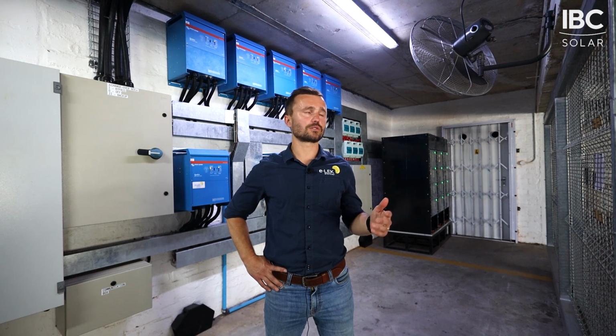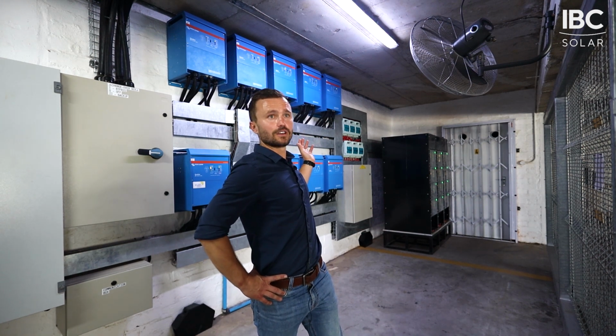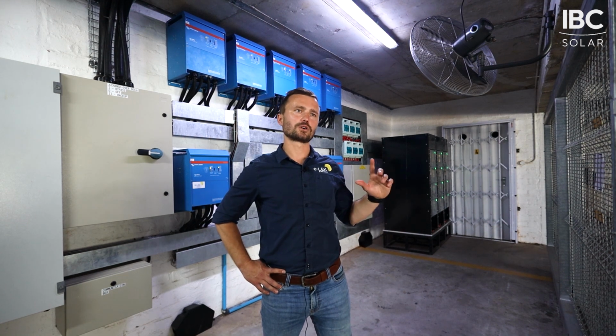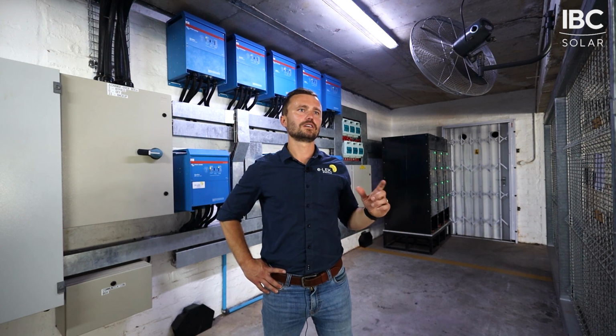What makes this installation unique is it's not just the solar that's contributing to their savings every month. We are actually utilizing our inverter and battery system to manage their demand charge each month, and because of their tariff structure, during peak times we discharge the batteries and during off-peak times we recharge them, which gives a massive saving on the electricity bill.